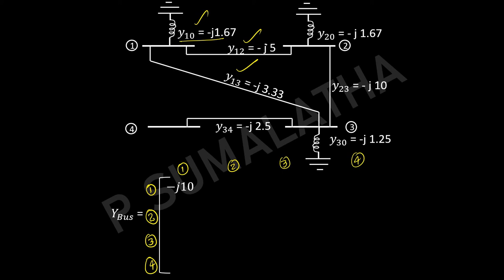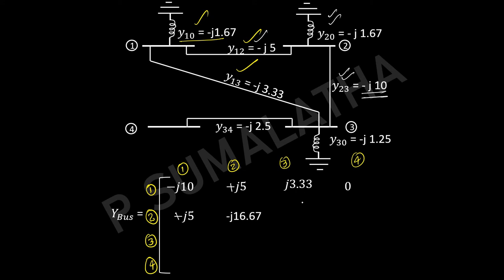Y12 equals plus J5. Y13 equals plus J3.33. Y14 equals 0 since there is no connection between buses 1 and 4. Y21 equals Y12 equals plus J5. Y22 is the sum of admittances connected to the second bus: minus J5 plus minus J1.67 plus minus J10 equals minus J16.67. Y23 equals minus of minus J10, giving plus J10. Y24 equals 0 — no direct connection between buses 2 and 4.